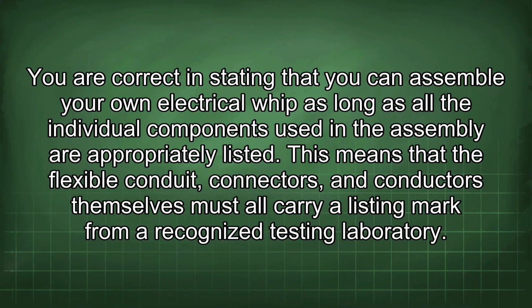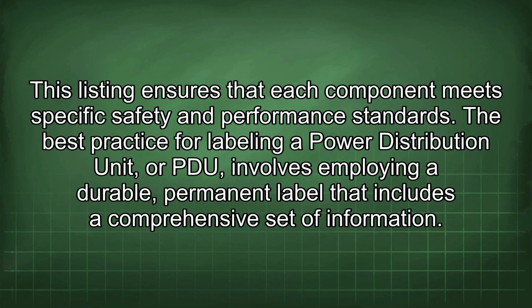You are correct in stating that you can assemble your own electrical whip as long as all the individual components used in the assembly are appropriately listed. This means that the flexible conduit, connectors, and conductors themselves must all carry a listing mark from a recognized testing laboratory. This listing ensures that each component meets specific safety and performance standards.